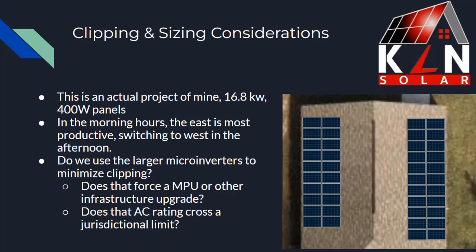In some places — I recently had a project in Colorado where AC ratings cross jurisdictional limits — if the system was above about 11 kilowatts, it was a wholesale net metering scheme; if below that, they got one-for-one. So now you have a trade-off using these same panels: what's more advantageous? If I use that lower AC rating, maybe I have a better net metering scheme and I don't need to pay for a main panel upgrade, but how much energy am I losing at the same time?